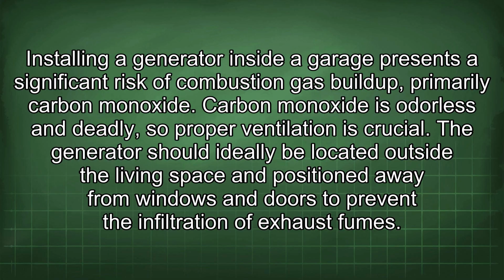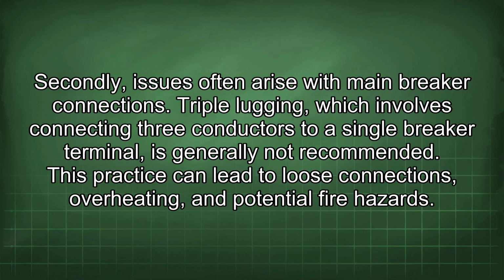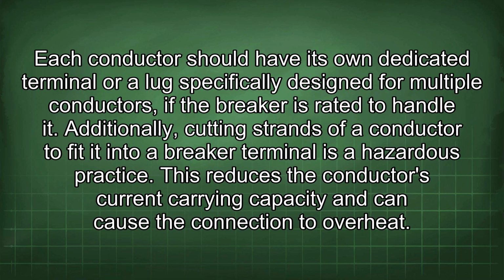The generator should ideally be located outside the living space and positioned away from windows and doors to prevent the infiltration of exhaust fumes. Secondly, issues often arise with main breaker connections. Triple lugging, which involves connecting 3 conductors to a single breaker terminal, is generally not recommended. This practice can lead to loose connections, overheating, and potential fire hazards.